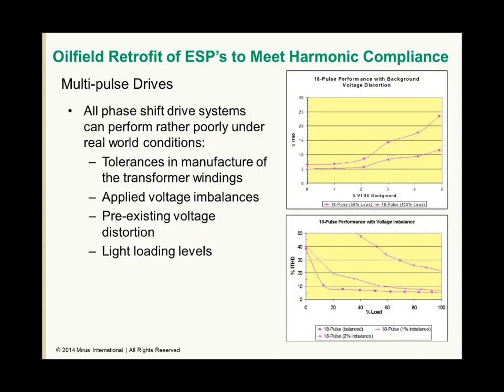The multi-pulse solution was ruled out due to the very poor performance that they achieve in real-world conditions when voltage distortion or voltage imbalance is high. This was evident in the fact that some of the ESPs were already equipped with 18 or 24 pulse VFDs. Their performance was so poor that they did not improve the overall distortion levels.